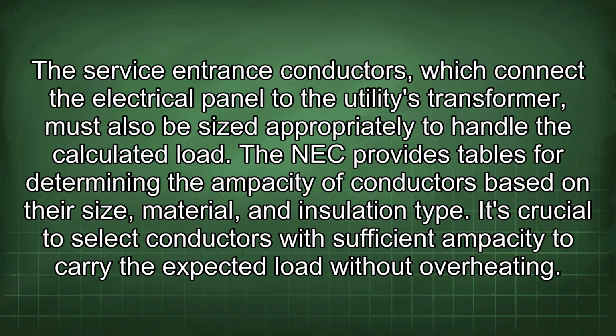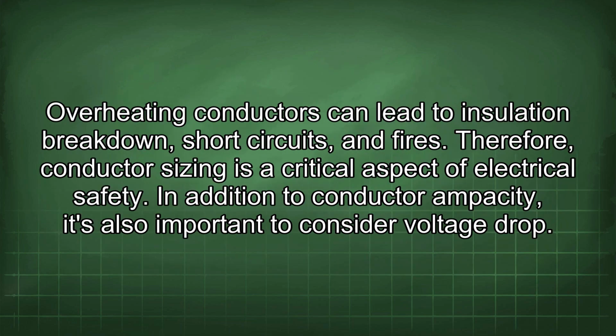The service entrance conductors, which connect the electrical panel to the utility's transformer, must also be sized appropriately to handle the calculated load. The NEC provides tables for determining the ampacity of conductors based on their size, material, and insulation type. It's crucial to select conductors with sufficient ampacity to carry the expected load without overheating. Overheating conductors can lead to insulation breakdown, short circuits, and fires. Therefore, conductor sizing is a critical aspect of electrical safety.